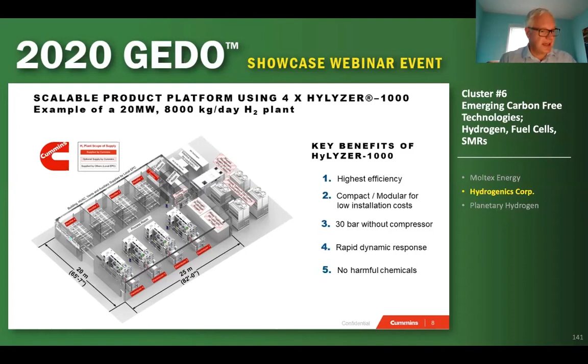We believe we've got a very compelling value proposition for this plant. It's the highest efficiency electrolyzer, highest power density, so it's got a low footprint. You can see that the core system fits in 500 square meters for 20 megawatts. It delivers 30 bar hydrogen output, while a number of our competitors deliver plants with atmospheric 1 bar output. PEM electrolyzers have a very fast dynamic response, that's why it works so well with the ISO providing regulation services, and there's no harmful chemicals involved.